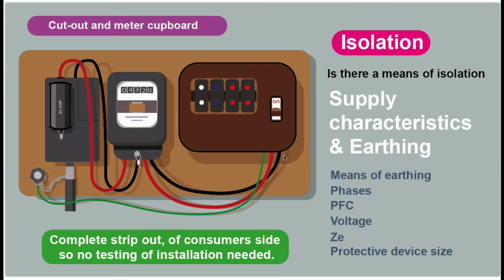And also, there's no means of isolation for this fuse board. We need to take this fuse board away, and there's no way we can isolate this to do it safely without pulling the main fuse. And technically, we're not allowed to pull the main fuse, but you can get the supply company to come and fit an isolator. So these are jobs that are good to start on straight away, and if there is an issue, we can get the various companies round to help us out.